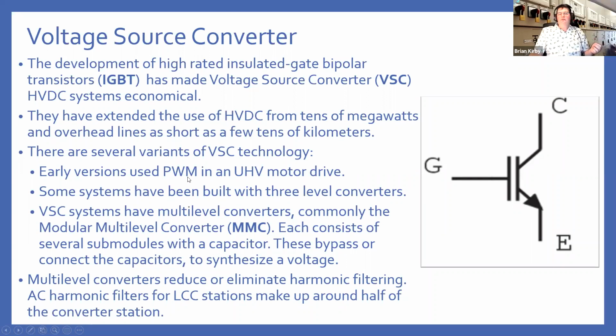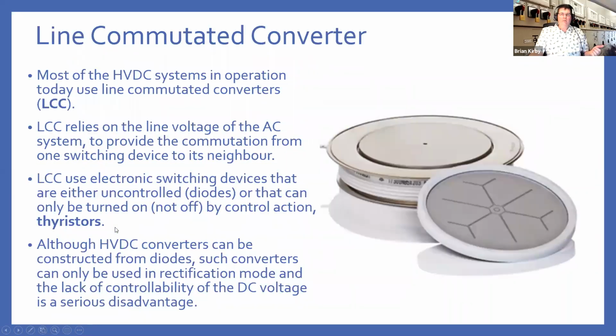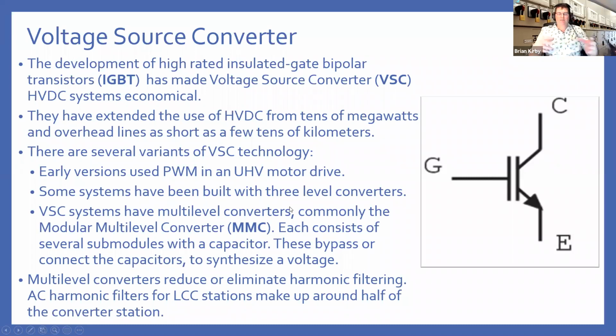There have been various evolutions over the years, starting with pulse width modulated versions in the early days. Today, the most common use is what's called modular multi-level converters, where you will build a module of a fixed voltage level, and then you stack them to build to the voltage level required. A typical module will be, say, 2000 volts, 2 kV, and capable of supplying maybe a few kiloamps when in operation. So when you stack them up, you can get significant amounts of voltage and current generated by these devices.